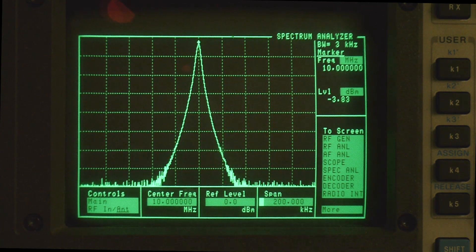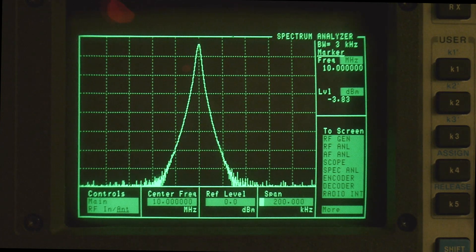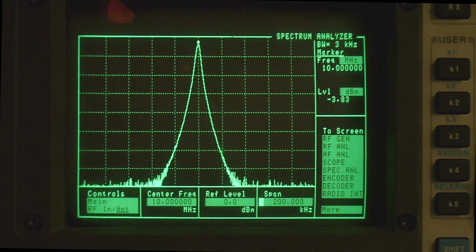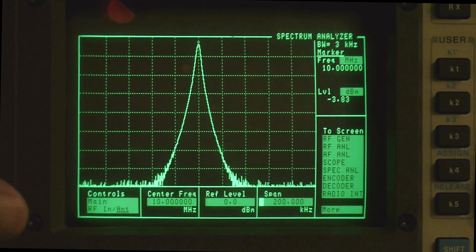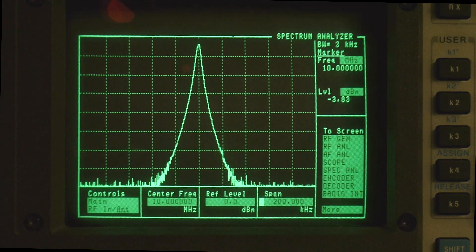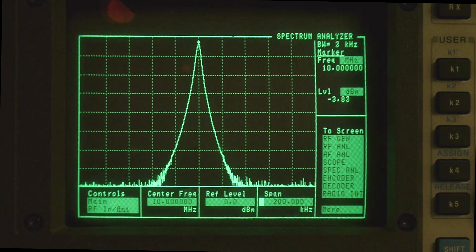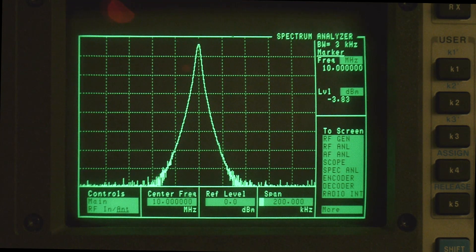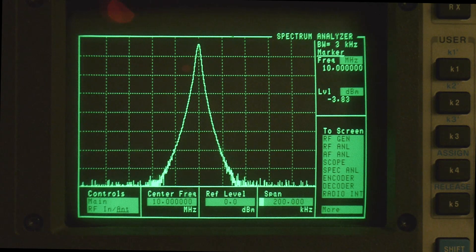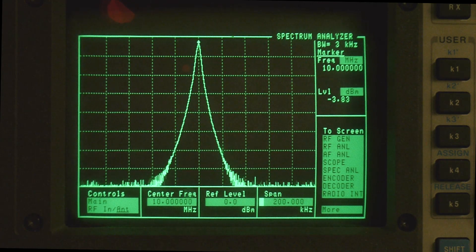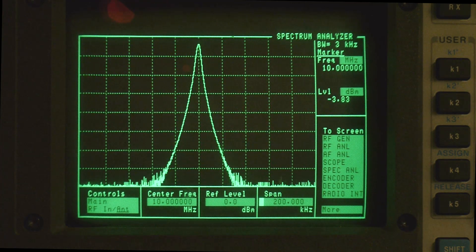Okay so you have to be worried about how much power you put into spectrum analyzers. You don't want to blow them up. They're very sensitive instruments. So this particular input that I'm using is good for 200 milliwatts. So if I go above 200 milliwatts I'm going to kill something. So I have to be really really careful. So if I start at 0 dbm and go down from there I'm in good shape. I'm either a milliwatt or below. So here's one milliwatt.